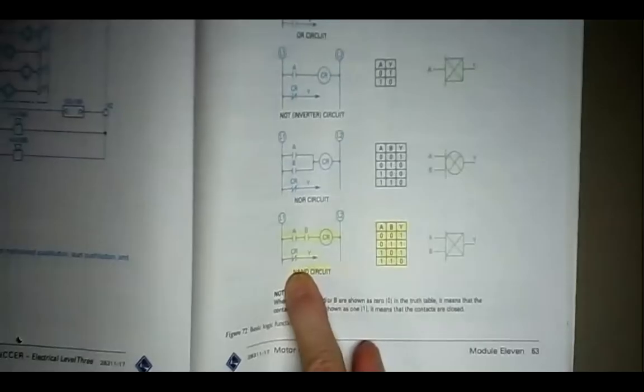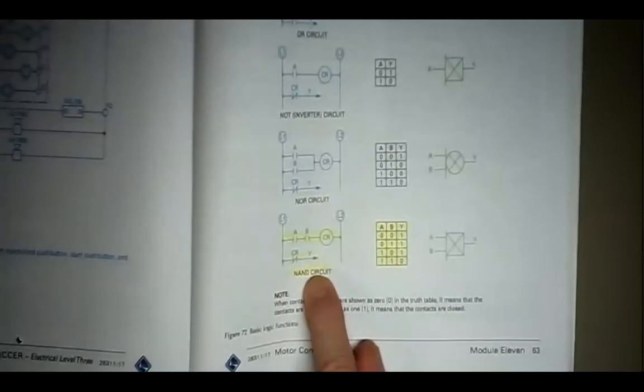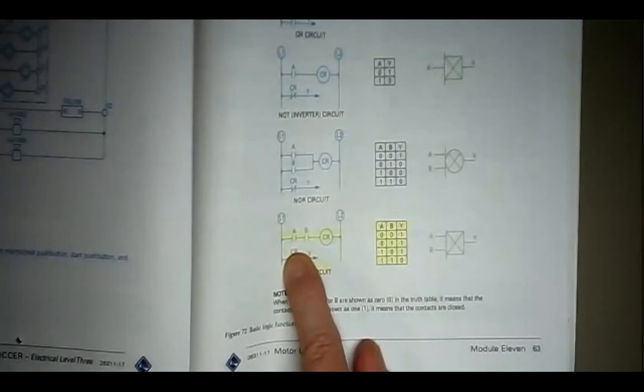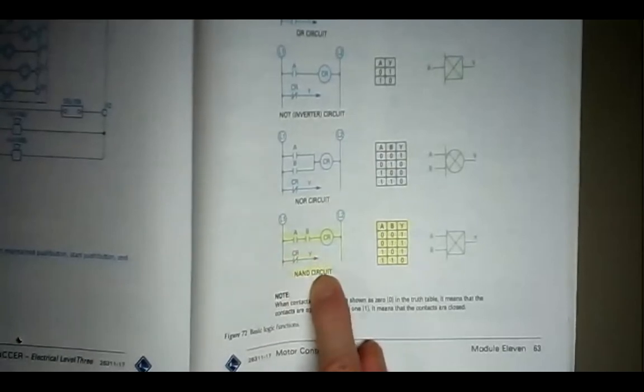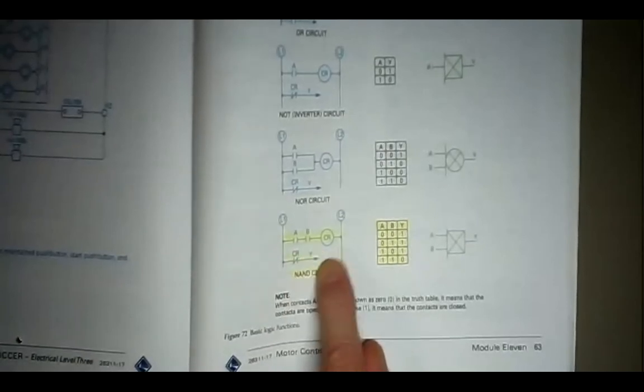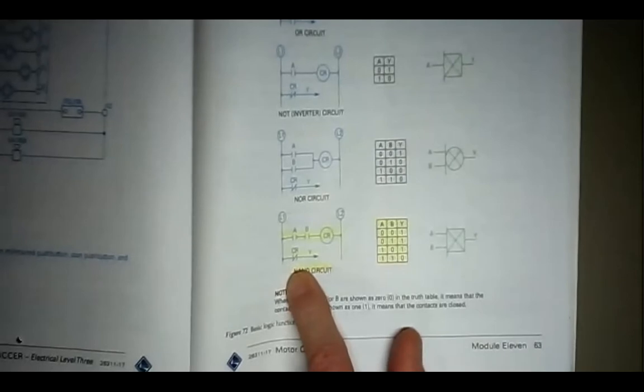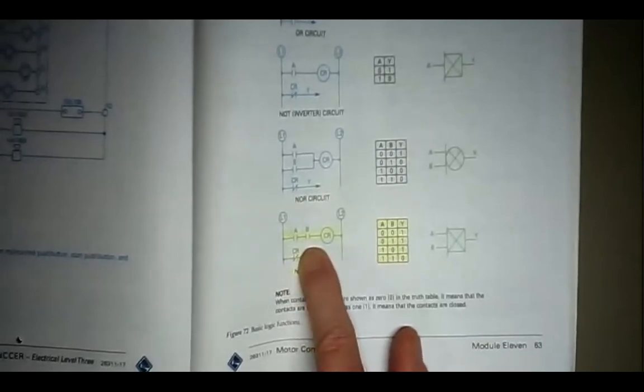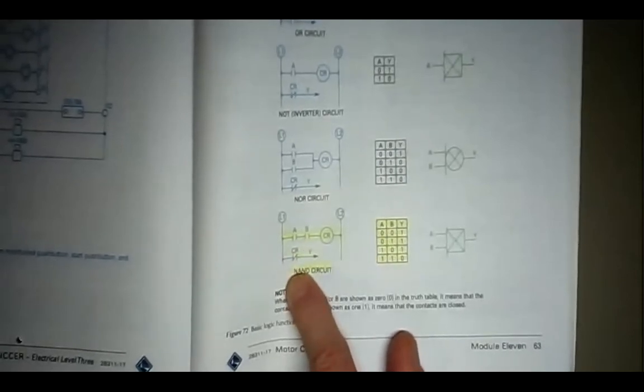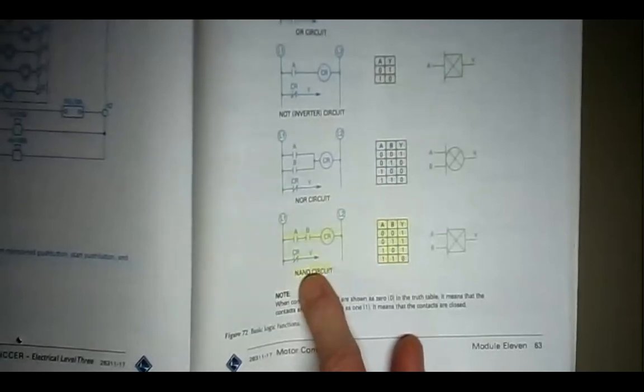I have a normally closed contact here from the control relay going to the output. So you can see that if I have A but not B, I still have an output. If I have B but not A, I still have an output. If I have neither A nor B, I still have an output. The only time I don't have an output is when I have both A and B inputs, and that opens this normally closed contact, turning off the output.